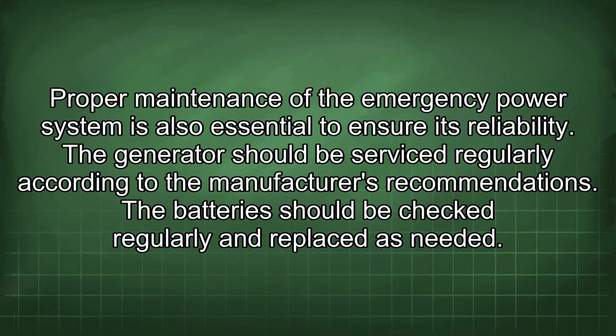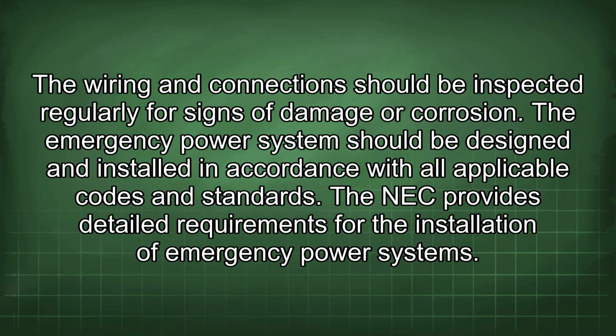Proper maintenance of the emergency power system is also essential to ensure its reliability. The generator should be serviced regularly according to the manufacturer's recommendations. The batteries should be checked regularly and replaced as needed. The wiring and connections should be inspected regularly for signs of damage or corrosion.